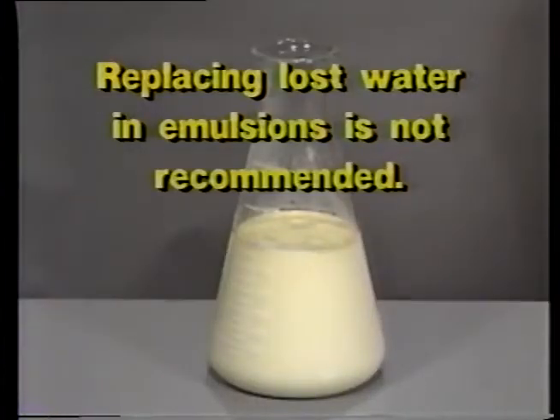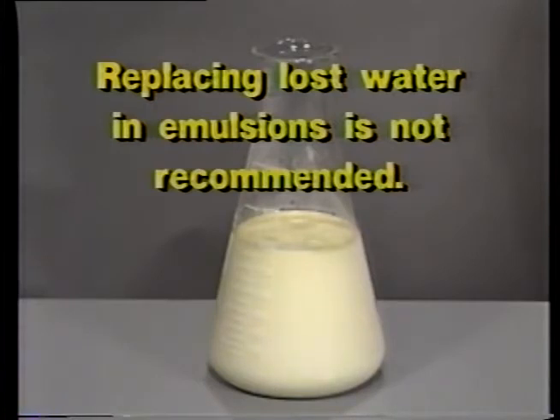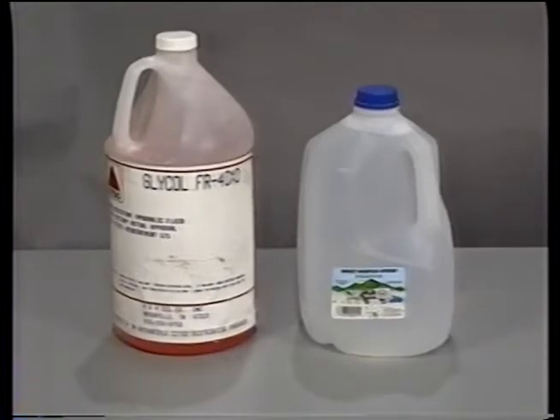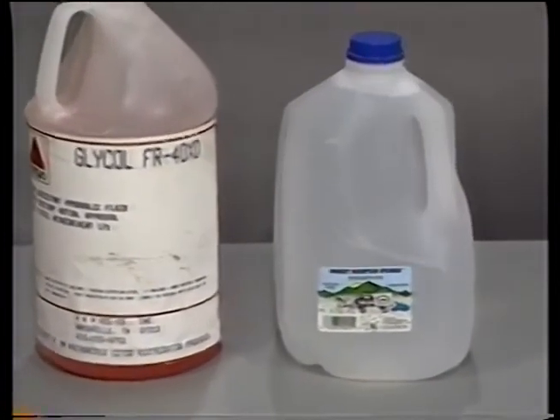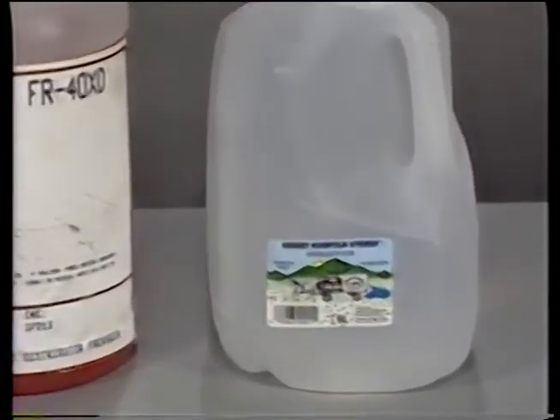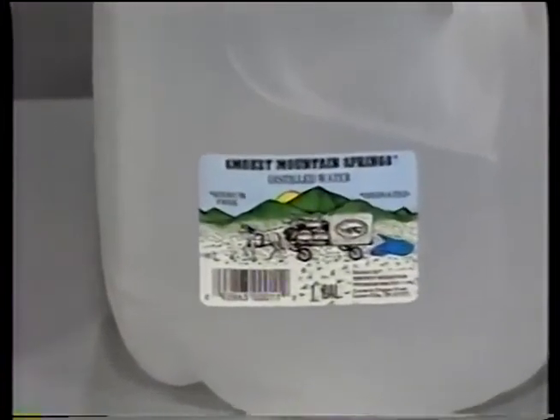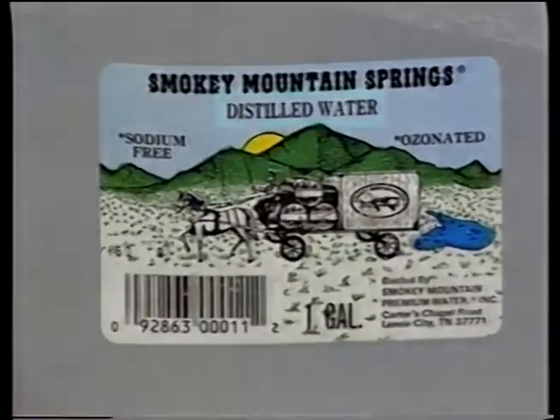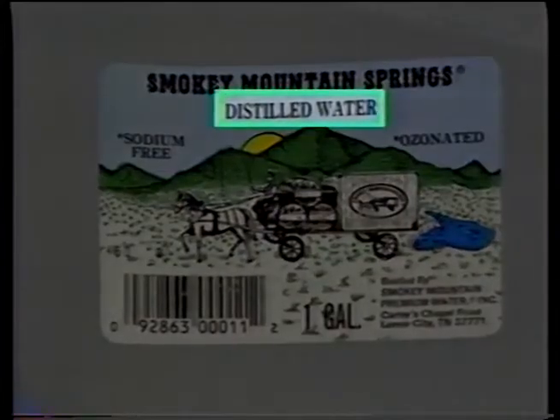Replacing lost water in an emulsion is not recommended. Without special equipment it is difficult to get the two substances to emulsify correctly and obtain the proper percentages of each. However, water can be replaced in water glycol solutions. But be careful where you get the replacement water — common tap water can contain chemicals and solids that can damage a system. If you have to add water to a water glycol fluid, make certain you use distilled or deionized water.